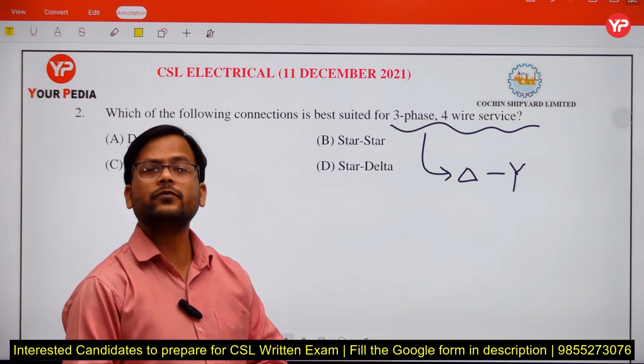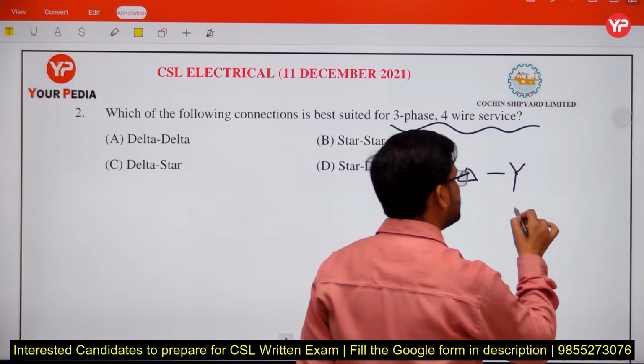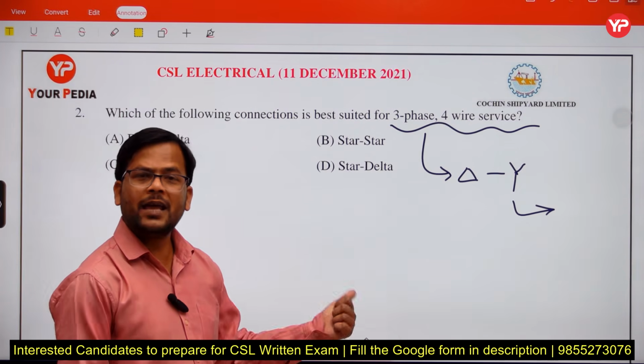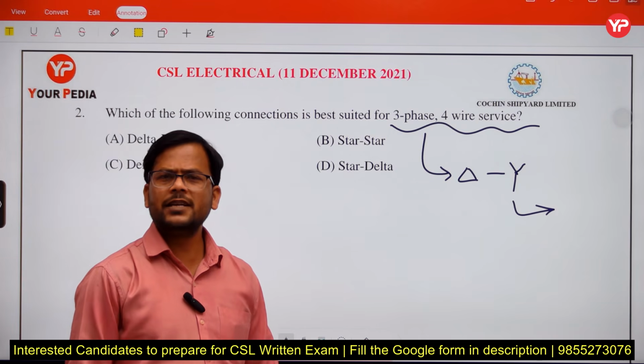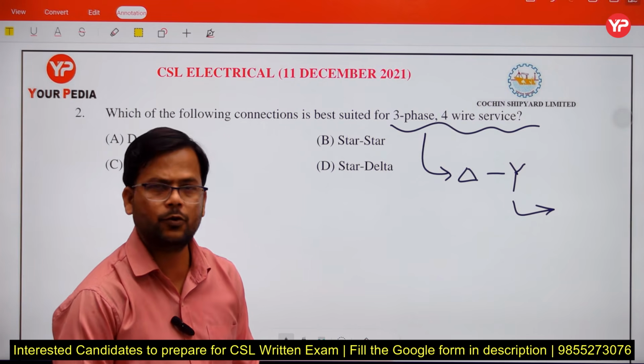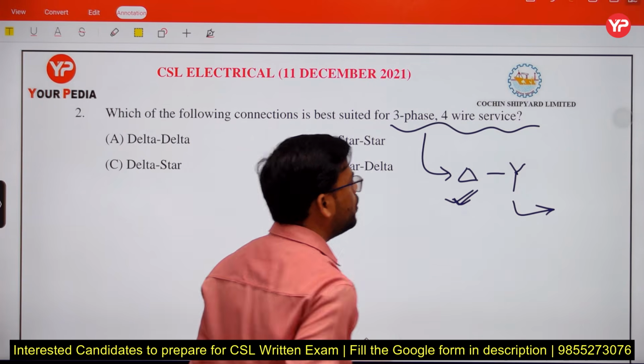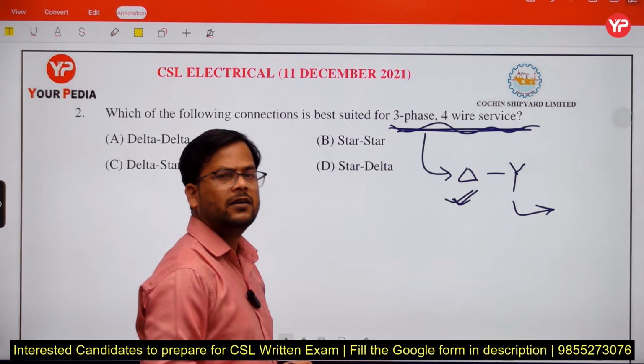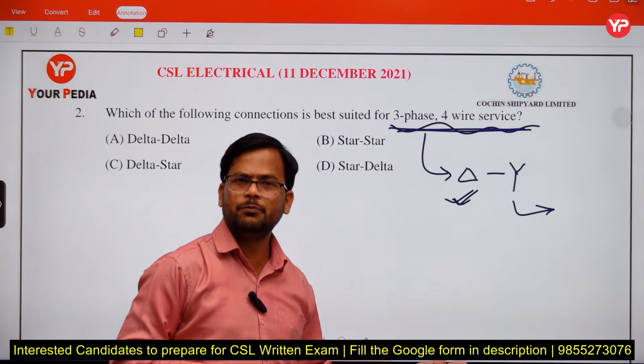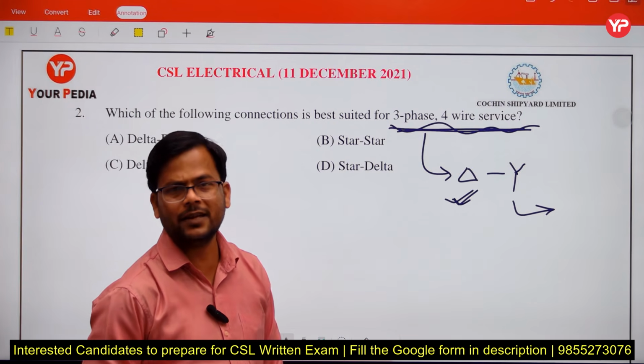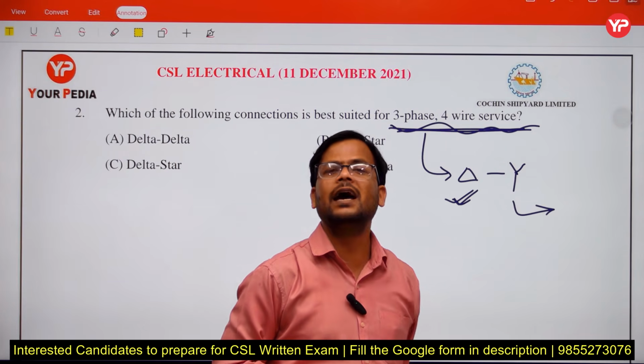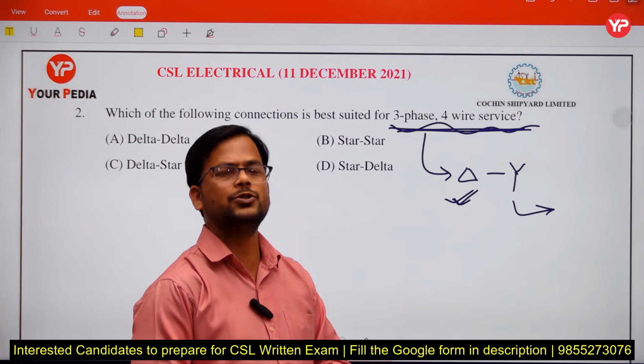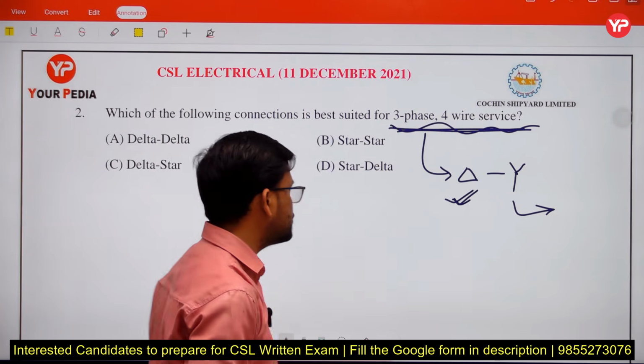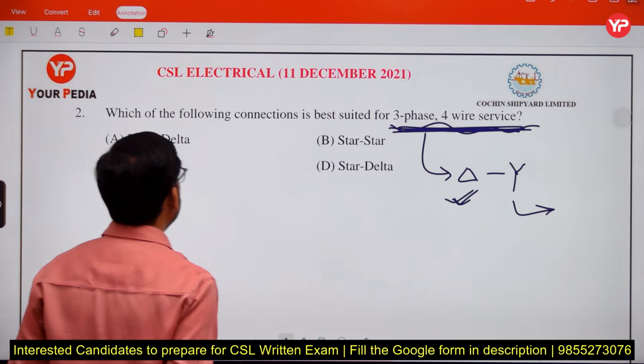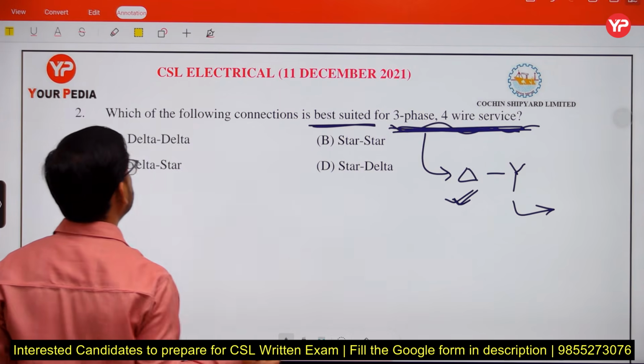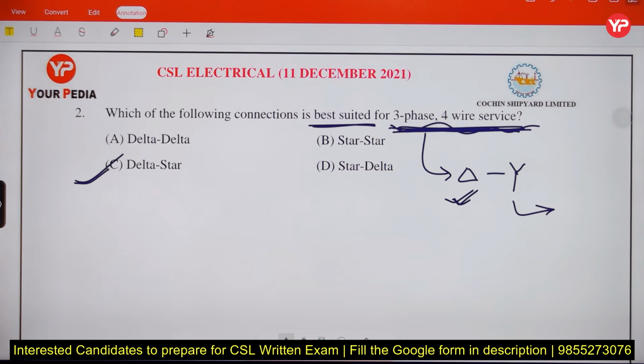That's why it provides a stable voltage. So the secondary must be a star connection and the primary must be a delta connection. The delta connection suppresses the harmonics. So for a 3-phase 4-wire system, to eliminate the harmonics we use delta connection in the primary, and to provide a stable voltage to the load we use a star connection on the secondary, because it has a neutral point. So the best suited connection for this is delta star. The correct answer is option C.